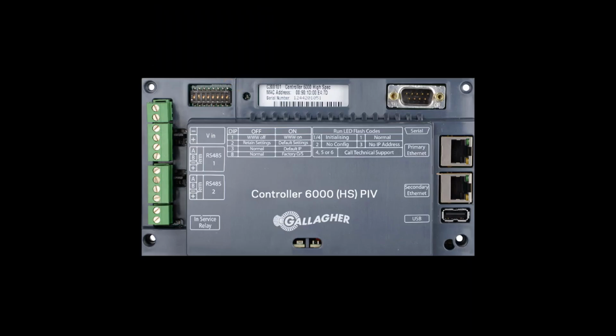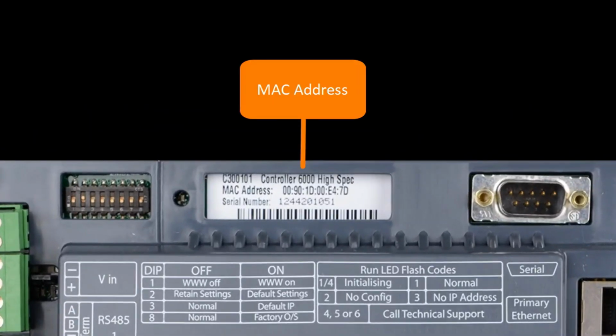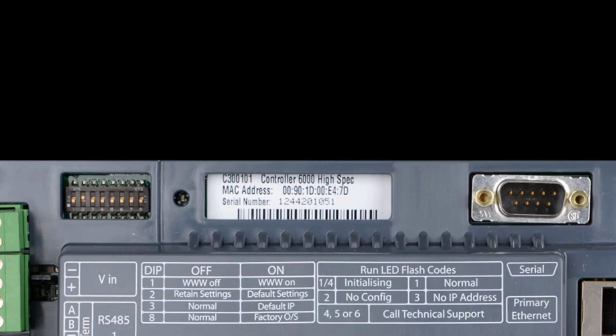Each controller has its own unique pre-programmed MAC address, which must be configured in Command Center for the software to acknowledge this Ethernet address and allow the controller to come online. When bringing a controller online, the MAC address can be taken from this window and configured within the software as part of the process of configuring and bringing Gallagher controllers online.